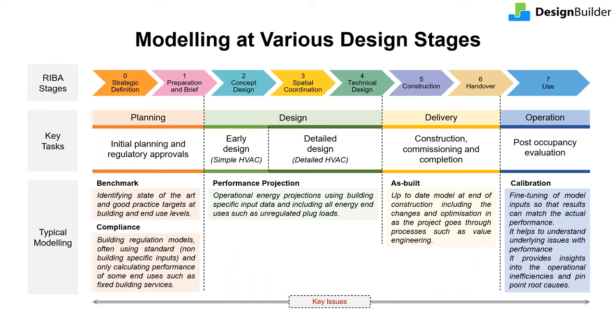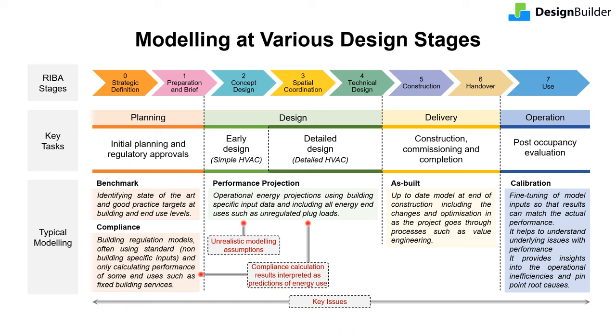Key issues that affect modeling and should be noted by modelers: compliance models are created for comparative assessment and benchmarking; however, results from compliance models are often mistakenly interpreted as predictions of actual energy use. It must be remembered that compliance models are often hugely simplified and their purpose is different when compared to performance modeling. Generic design and operational assumptions are often used in compliance models, whereas building-specific model data should be used in performance modeling.